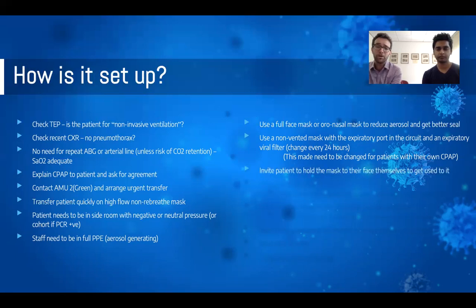So the first thing to do with the patient is to invite them to hold the mask to their face, partly to measure it up and so that they can get a feel for what that's going to be like. And then the sequence of actions here is really important and slightly different to how we'd normally do it. So with the mask held to the patient's face with a good seal, then turn on the machine, the ventilator. And similarly, when you want to take the mask off, turn the ventilator off first and then the mask away. What we're trying to prevent is having a mask that's contaminated with the patient's secretions and the ventilator on and just dispersing that around the room.